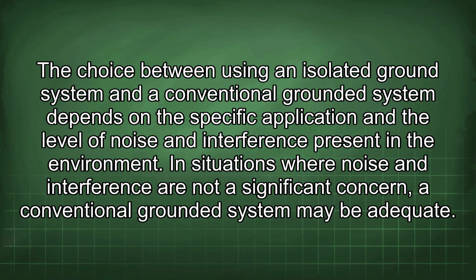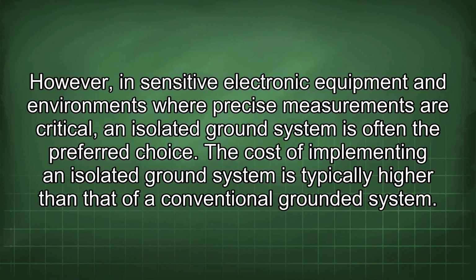The choice between using an isolated ground system and a conventional grounded system depends on the specific application and the level of noise and interference present in the environment. In situations where noise and interference are not a significant concern, a conventional grounded system may be adequate.